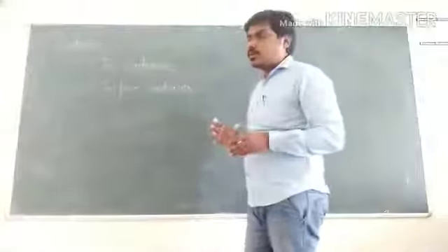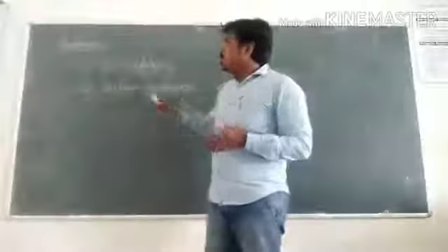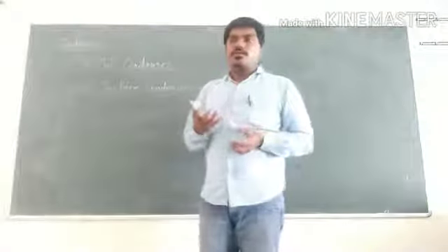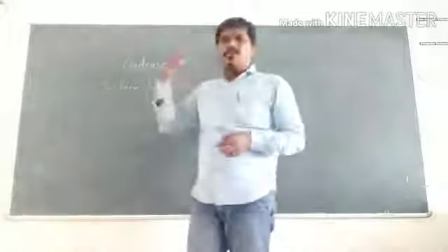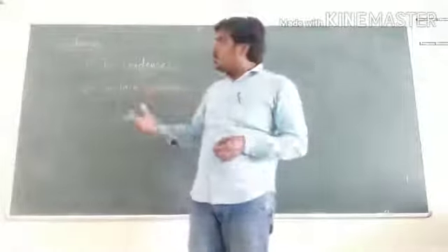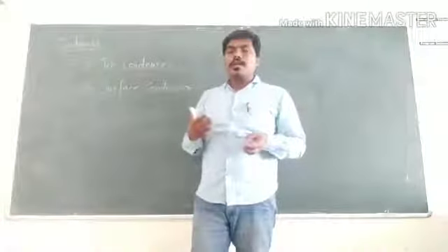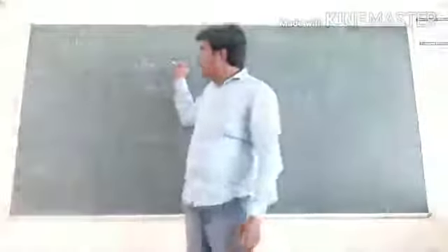But you should know that the condenser is also an important component in the thermal power plant, because the main source of steam is water. So we need that water. I want to reuse my water again and again. So with the help of the condenser only, I am going to collect my steam and convert my steam into water, by extracting that heat. So it is classified into two types: jet condenser and surface condenser. These two condensers are important.